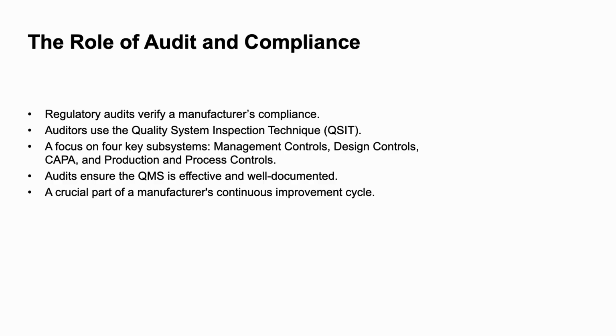For example, during an audit, an inspector might review a company's CAPA system to ensure that all non-conformances and complaints are properly investigated and that corrective actions are effective. The auditor will look for objective evidence that the QMS is being followed, which includes reviewing records, procedures, and work instructions. In Canada, while Health Canada does not use QSIT per se, it conducts inspections based on ISO 13485:2016, which aligns closely with the principles of QSIT. The auditor will review the company's QMS to ensure that it meets the requirements for licensing and market access.